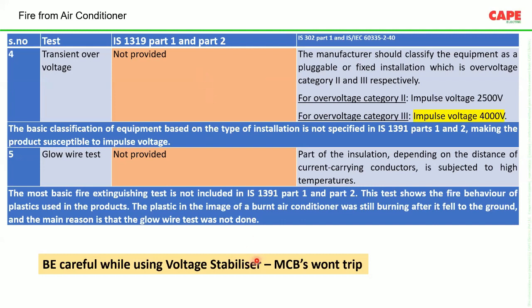And when you install it, be very careful about the voltage stabilizer. If you use a voltage stabilizer, instantaneous tripping of MCBs may not happen. During a short circuit, the MCBs may not trip instantaneously. Of course, overload protection is possible, but instantaneous tripping may not be possible because voltage stabilizers add impedance in the circuit. As a result, the fault current, or short circuit current, is reduced and the disconnection time will be higher, resulting in a fire. You have to be very careful.